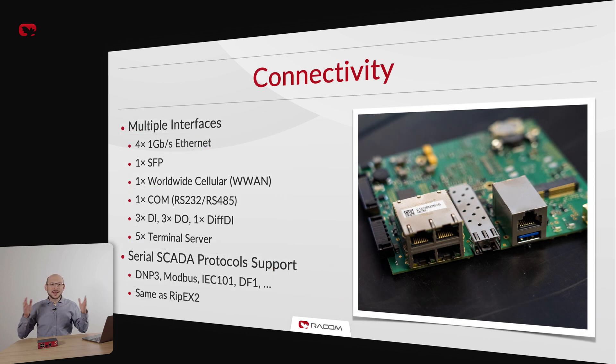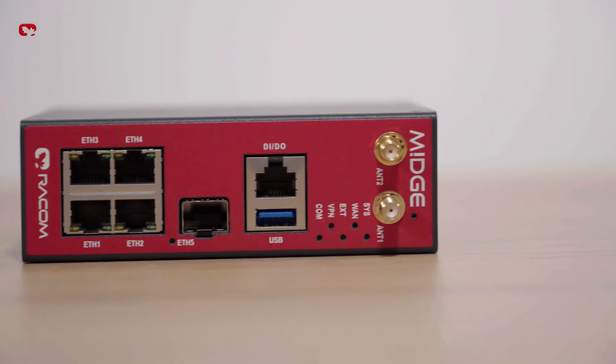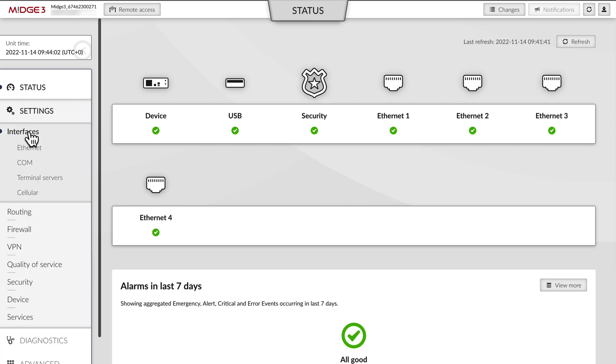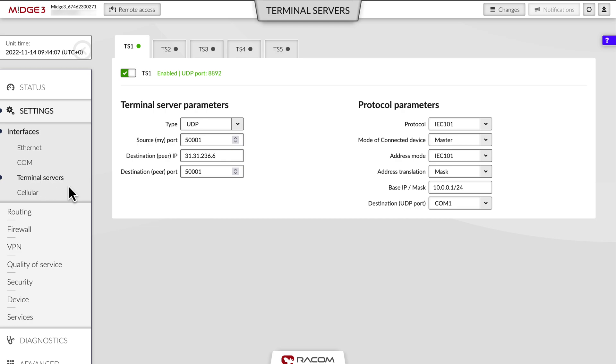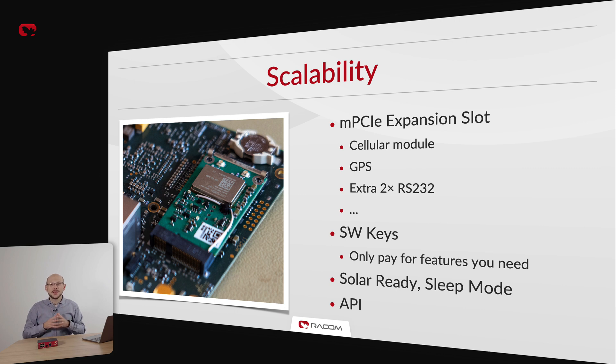Midge3 offers the widest range of interfaces to date: 4 gigabit Ethernet, 1 SFP, and up to 3 serial ports, digital inputs and outputs, and 5 terminal servers simplifying serial SCADA communication over IP networks. Serial SCADA protocols like DNP3 or IEC 101 are 100% the same as in RipEX2, making the units ideal for hybrid networks. Midge3 can also be combined with previous generation cellular routers and radio modems for easy gradual upgrades. We also include a mini PCIe expansion slot where you can mount GPS, extra serial ports, or another cellular module to further extend Midge3 functionality.